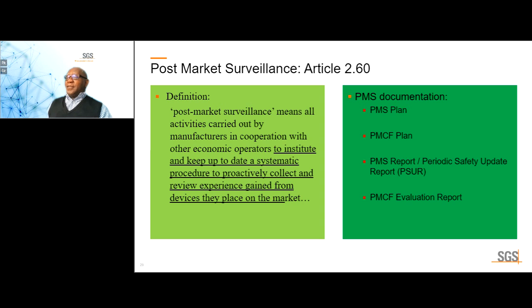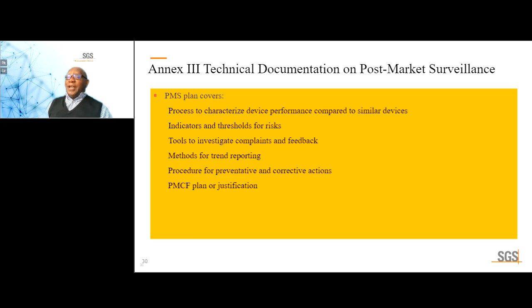So PMS requires its own documentation. You need a plan, a post-market clinical follow-up plan. This is part of proactive PMS. If you have a plan, you're going to have corresponding reports. So you need a PMS report, including a periodic safety update report and a PMCF evaluation report. So the PMS plan covers the following: process to characterize your device performance as it compares to similar devices, thresholds for risks, how to investigate complaints and feedback. Remember, complaints and vigilance will be in the reactive PMS branch. Methods for trend reporting, procedures for preventive and corrective actions, and your PMCF plan, post-market clinical follow-up plan, or a justification if you feel you don't need it.